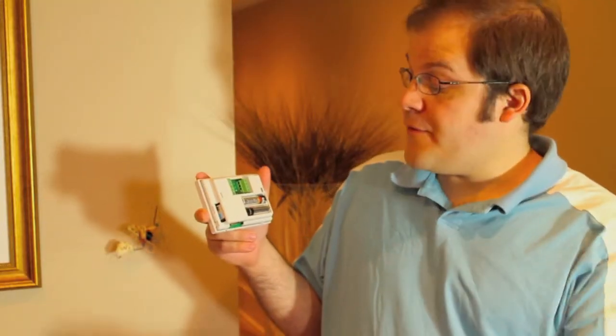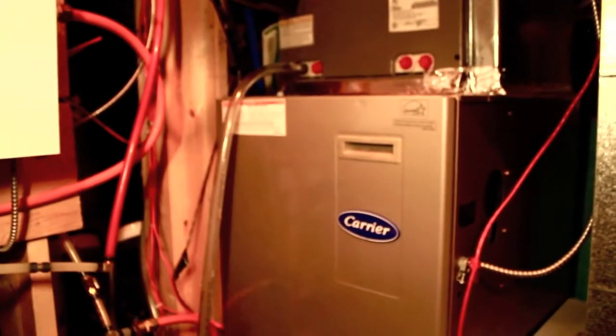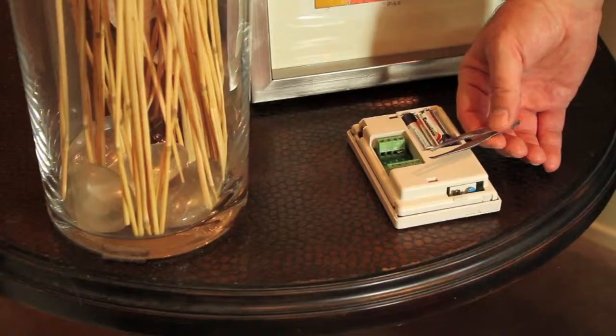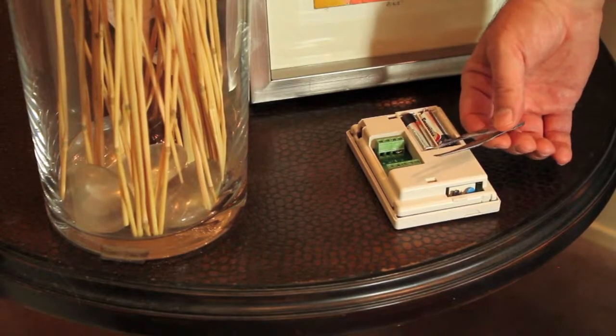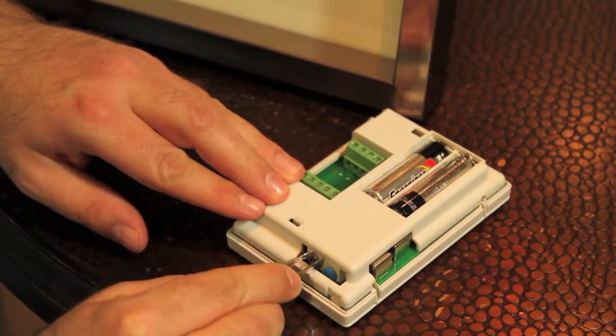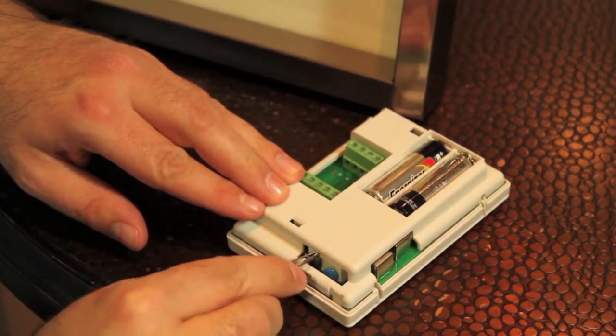Take a look at the fan operation jumper also on the back of the thermostat. If you're using a gas furnace the jumper should already be in the HG position. You may wish to use tweezers to grab hold of it. If you're using an electric furnace remove the jumper and place it in the HE position.